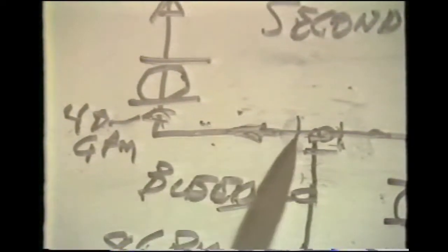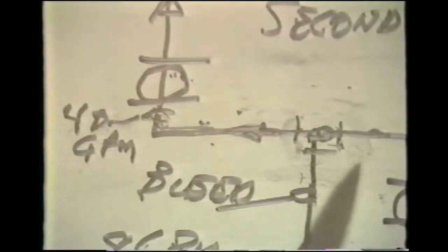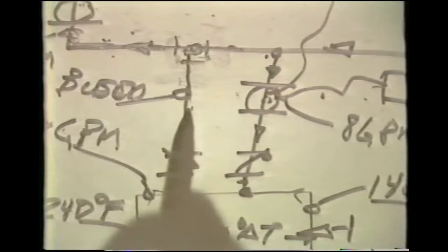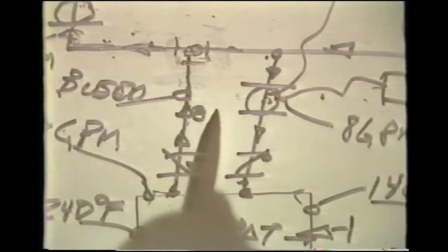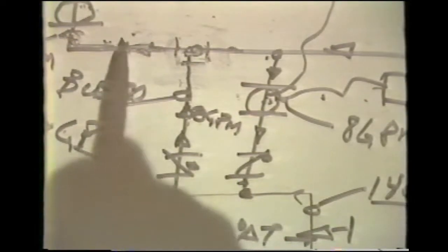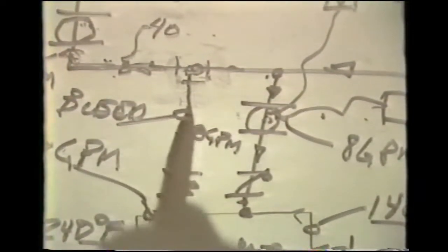We will have, as you remember, a flow rate of 40 GPM pumping out of that T and into the secondary circuit under the influence of the secondary circuit pump. Now, into the bottom of that T, we will, under the influence of the injection pump, provide 8 GPM flow rate. So we're leaving at 40, injecting 8, which really means that we must now provide a bypass, or this will automatically happen, of 32 GPM.